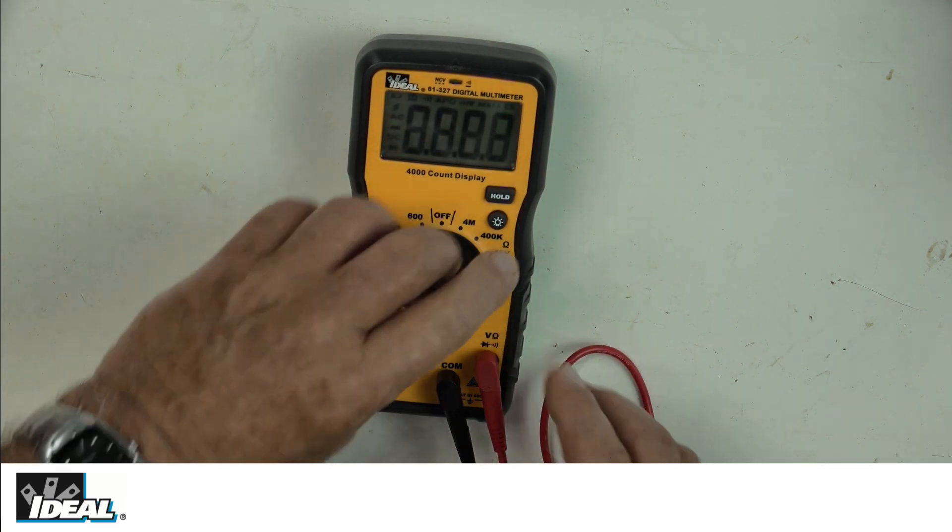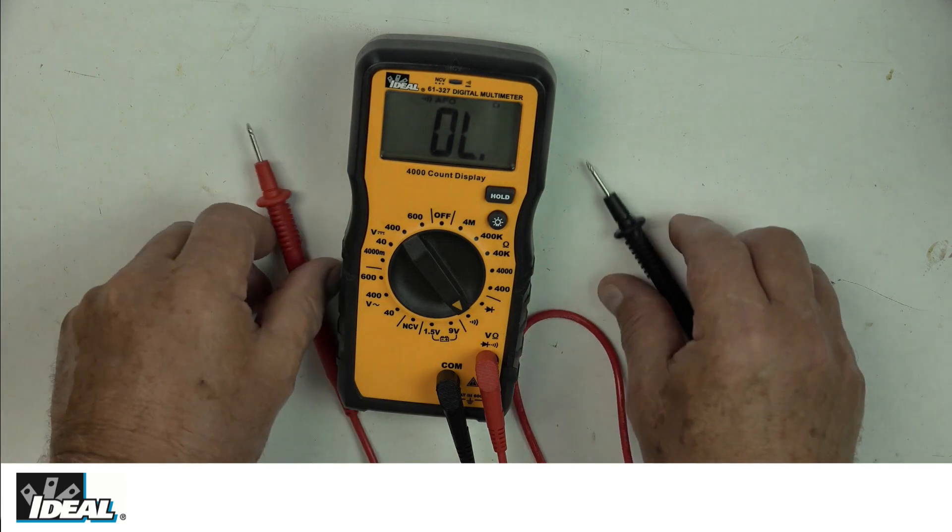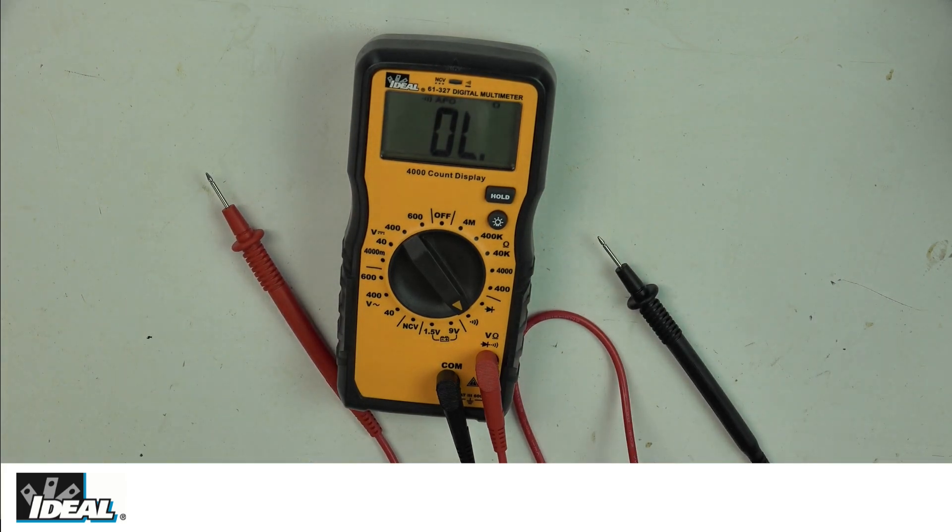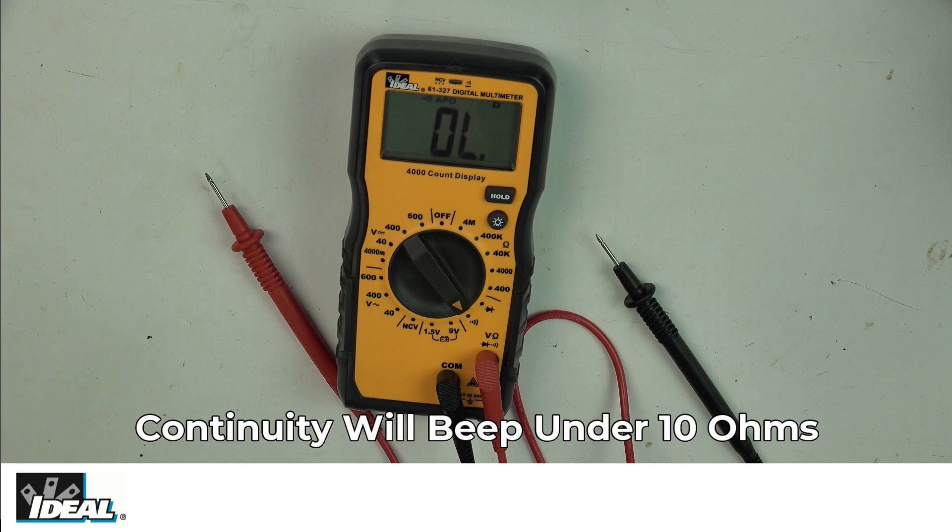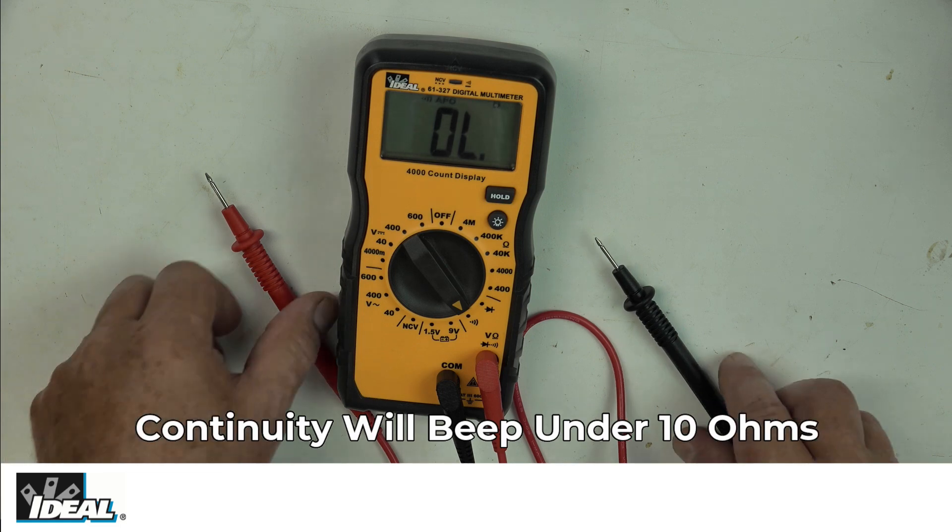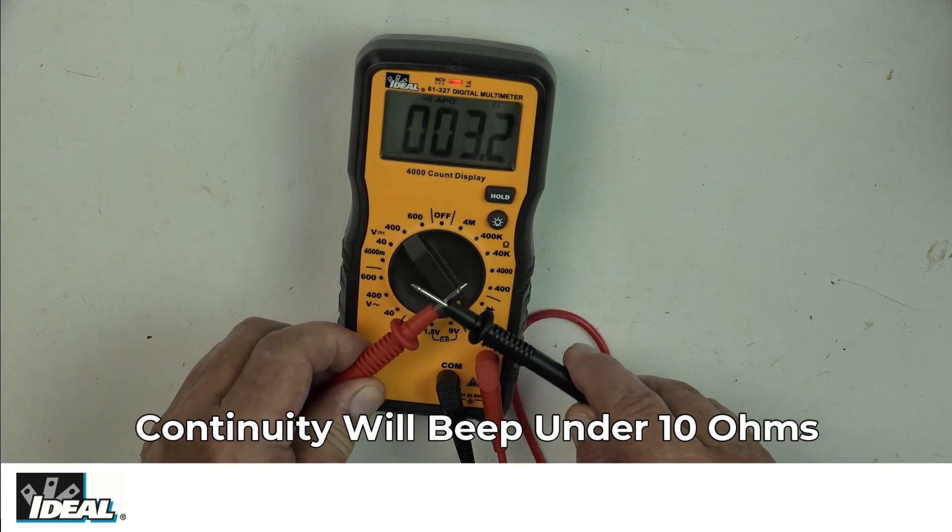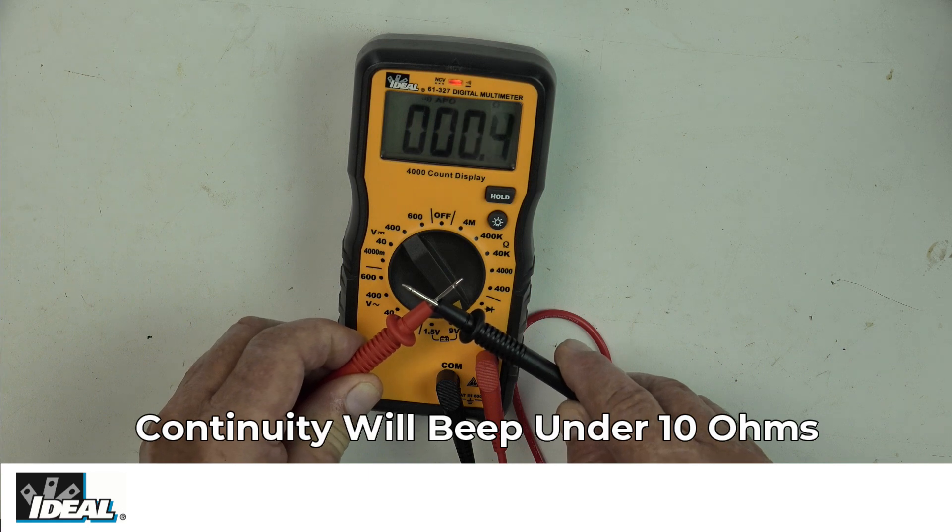Let's talk about continuity. If I put the tester in continuity, you get the audible symbol in the display. Right now it says OL or over limit. It's measuring resistance or ohms in continuity, so continuity is basically measuring ohms. On these testers, anything under 10 ohms or less will give you an audible tone. The meter pretty much zeroed out on us there, which it should, and gives you an audible tone.